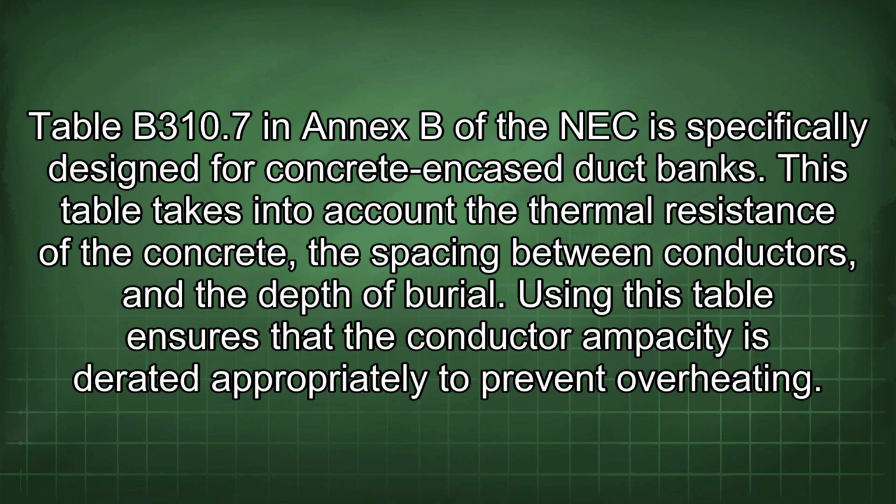Table B310.7 in Annex B of the NEC is specifically designed for concrete-encased duct banks. This table takes into account the thermal resistance of the concrete, the spacing between conductors, and the depth of burial. Using this table ensures that the conductor ampacity is determined appropriately to prevent overheating.